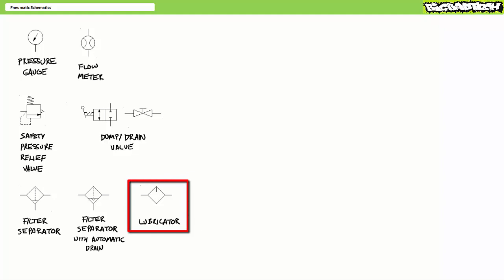Lubricators are schematically represented as a diamond with a line hanging off the top. Since air is not inherently self-lubricating like oil and hydraulic systems, lubricators periodically apportion a small squirt or fine mist of oil to the compressed air entering a pneumatic circuit. The introduction of oil into the airstream ensures the dynamic seals between moving actuators and valves remain functional. Systems lacking lubricators may necessitate technicians performing regular maintenance to periodically manually lubricate individual components to ensure their reliable operation.